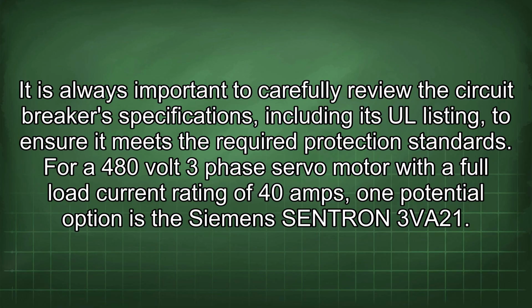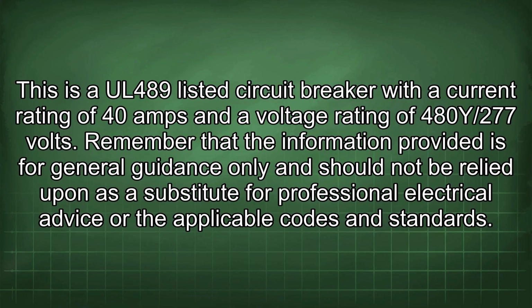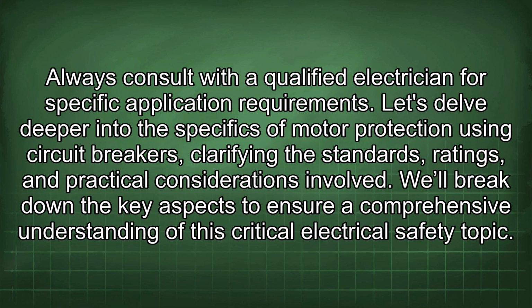For a 480 volt 3-phase servo motor with a full load current rating of 40 amps, one potential option is the Siemens SENTRON 3VA21. This is a UL 489 listed circuit breaker with a current rating of 40 amps and a voltage rating of 480/277 volts. Remember that the information provided is for general guidance only and should not be relied upon as a substitute for professional electrical advice or the applicable codes and standards. Always consult with a qualified electrician for specific application requirements.